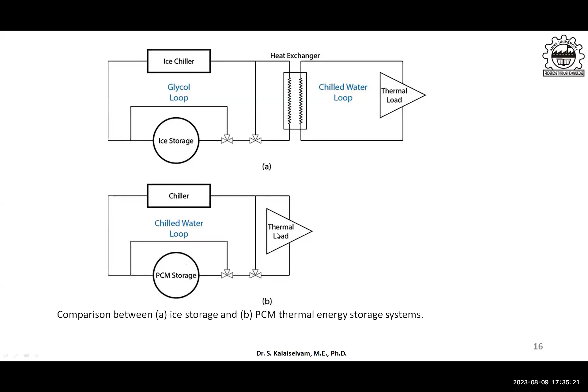We can also use ice storage as a phase-change material. Normally with ice storage we may require a primary and secondary fluid, but if we use phase change material, we can use only a single loop. Even the chilled water supply itself is more than sufficient to cater to the thermal load. That is why phase change material storage is always preferred for cold storage applications.